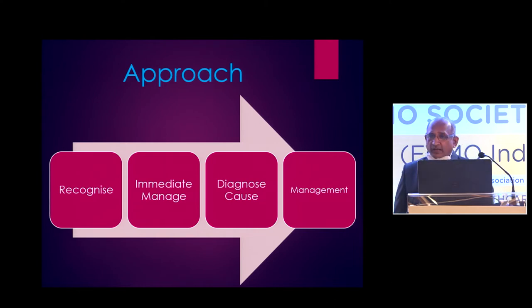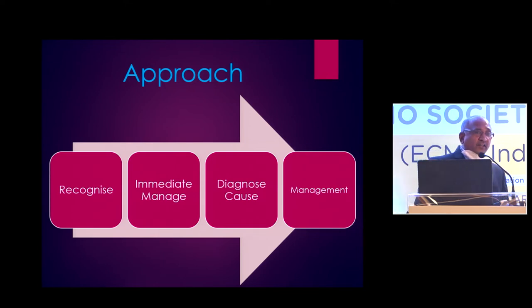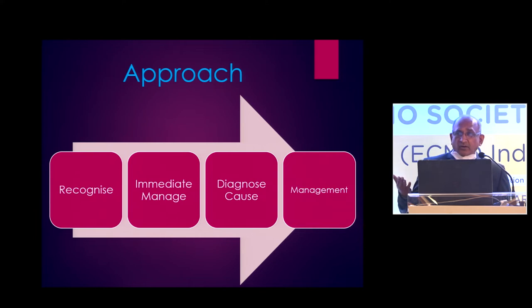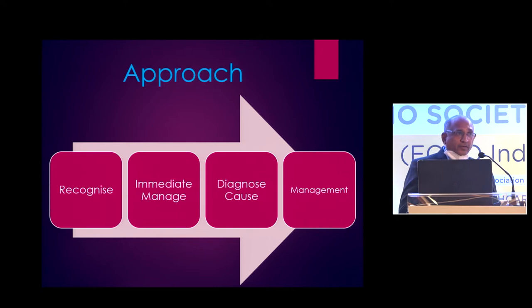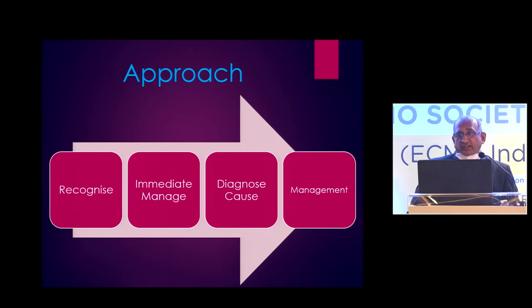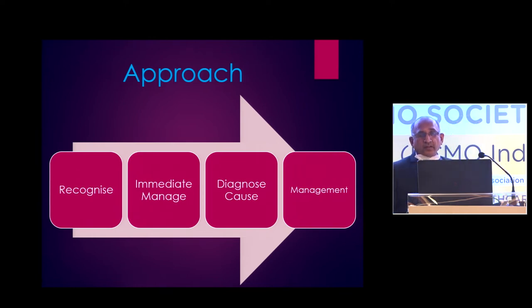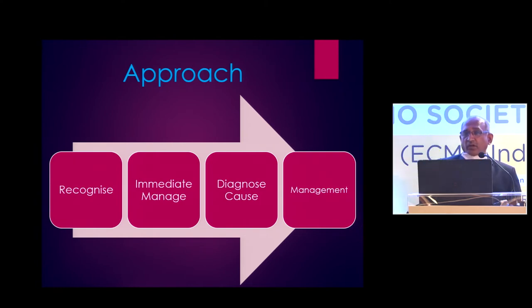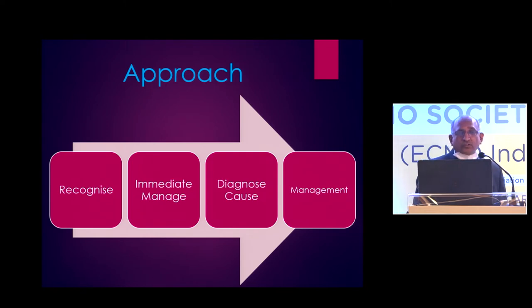So first you have to recognize the problem. Second, see whether it requires immediate attention and immediate management. For example, accidental decannulation will require immediate management. If there is a big clot in the pump and the pump stops suddenly, it requires immediate management. Third, diagnose the cause — what has led to this, why this event has occurred. Fourth, manage that particular event so that it does not repeat again. This is the way you should approach troubleshooting.